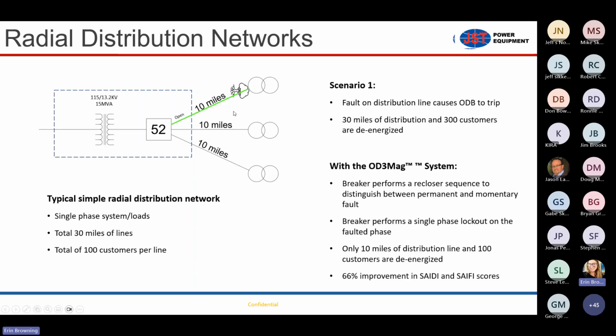And then if it's a permanent fault, if that tree fell over, you can actually just lock out one of the lines completely and the other two stay fully energized. So now again, you have a huge impact on the number of customers that are being affected. In this case, if we had 100 customers per line, now you're only affecting 300 customers instead of 900. So that's a 66% improvement on safety right there.